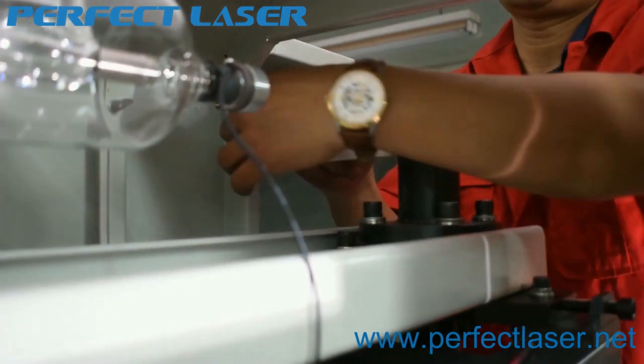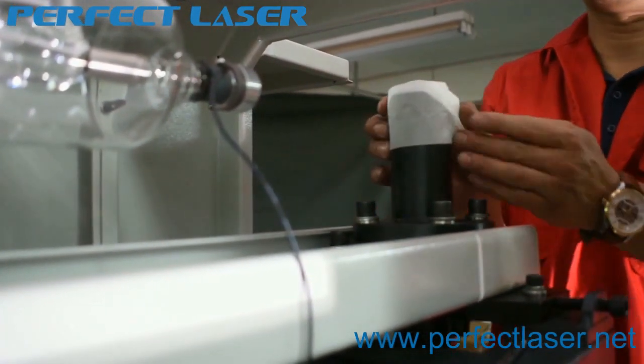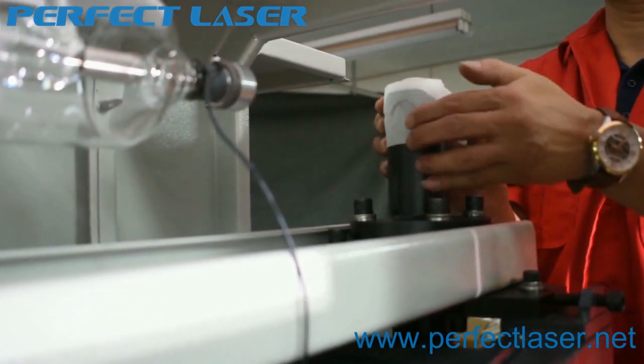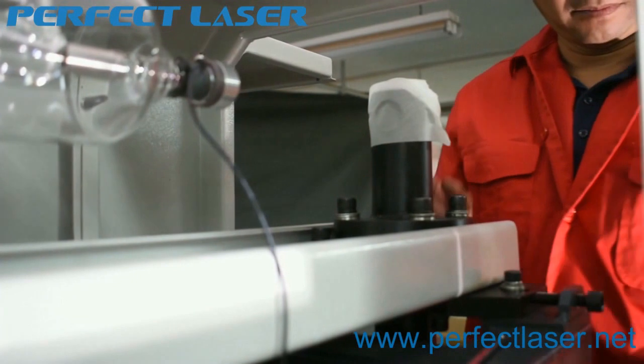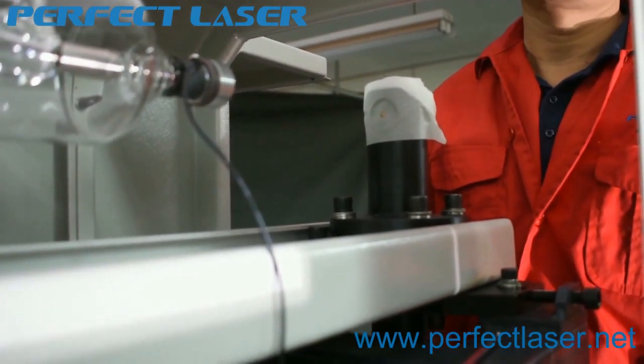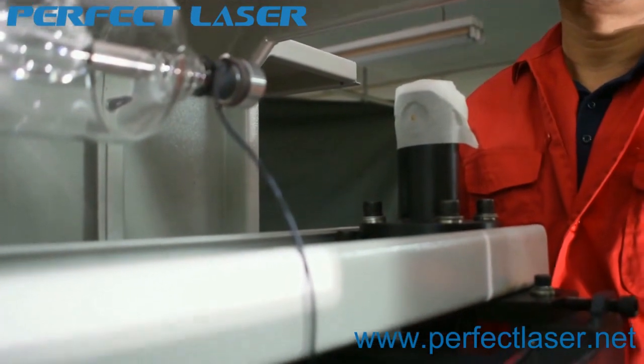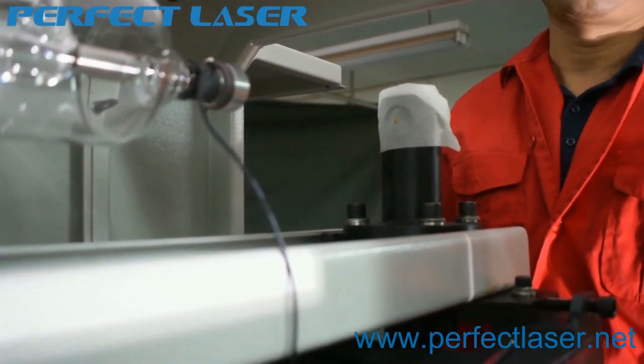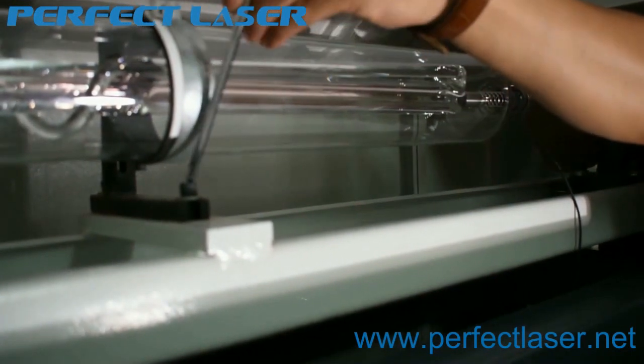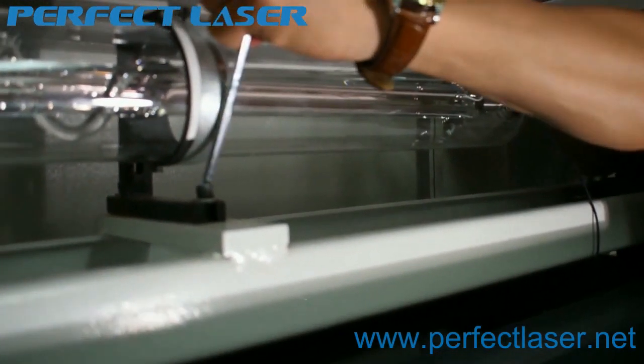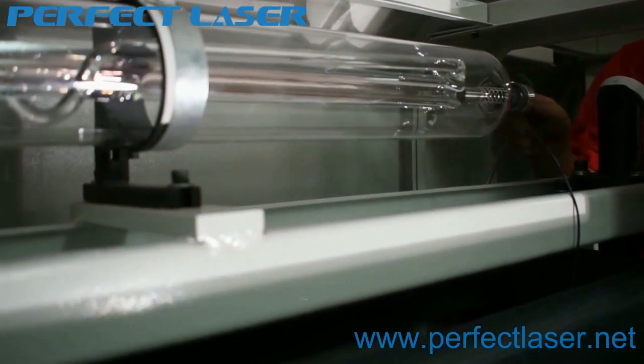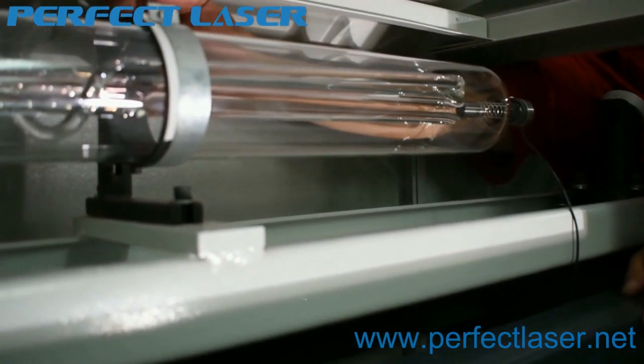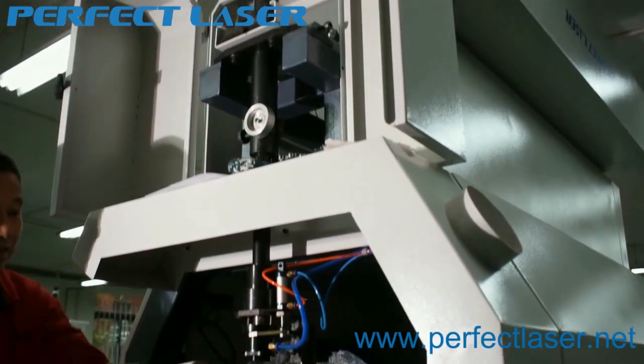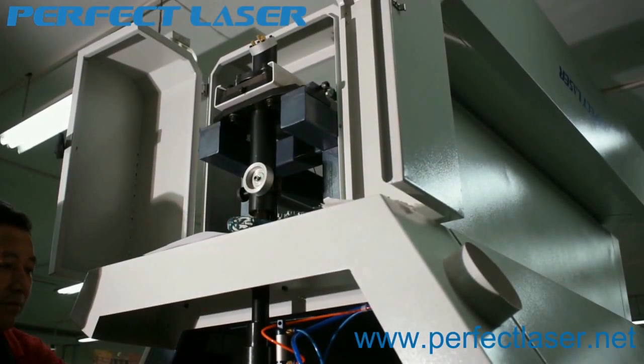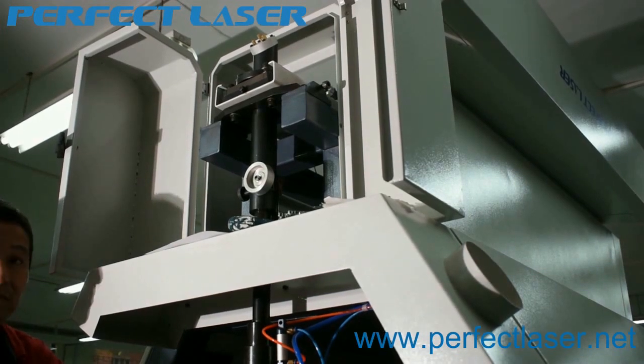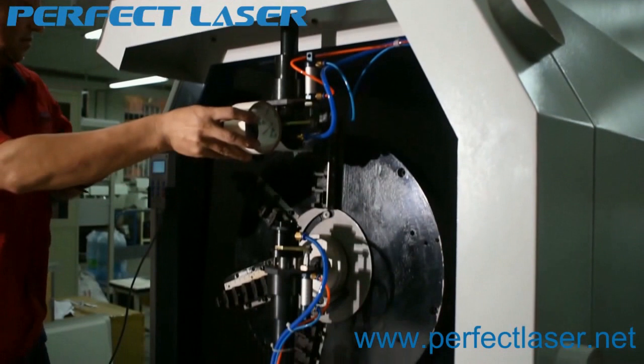We change another tape, and use your hand to make a circle, and press the DSP panel. Now it's somehow in the center of the circle. So now the laser tube align is okay. We fix the laser tube holder to make sure the position is fixed. After we make sure the laser beam comes out in the center of the reflect mirror, we will align here.